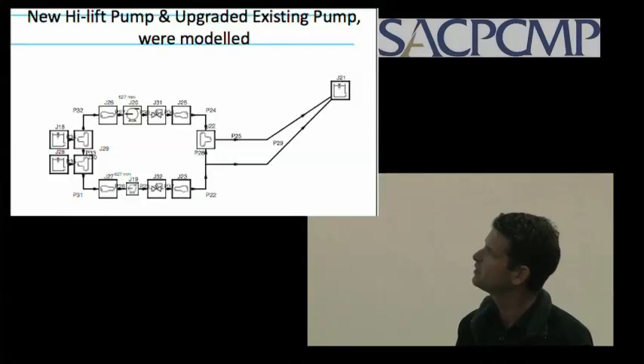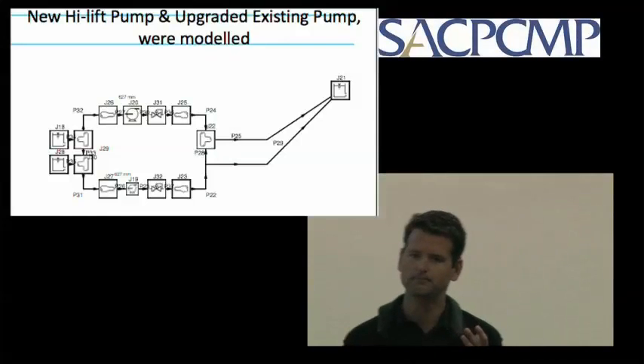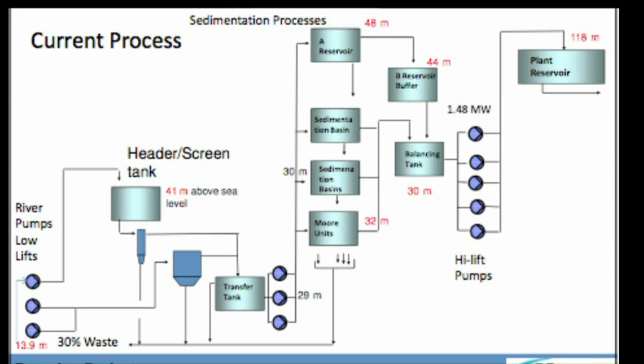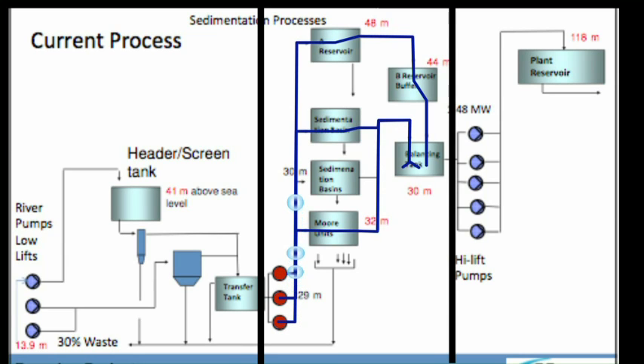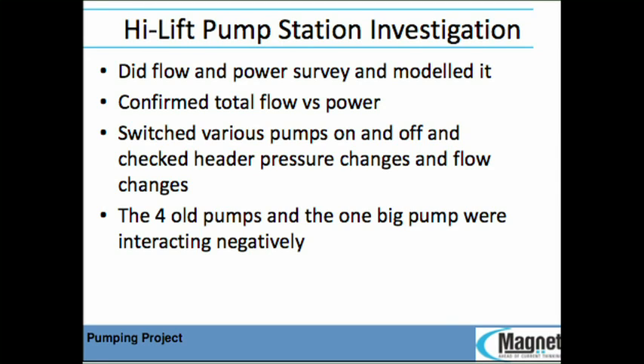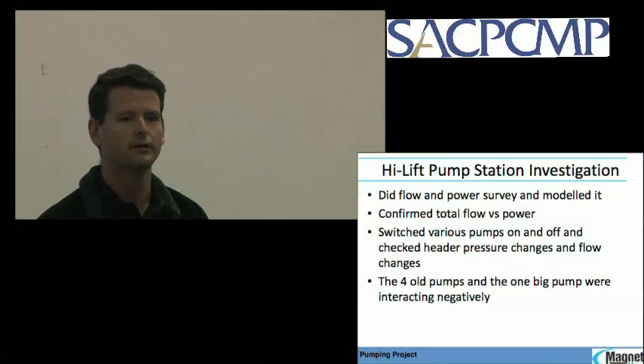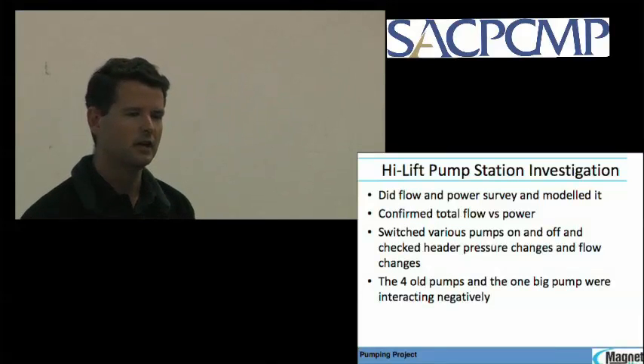The transfer pumps were also supplying this classic situation of pumping up to the A reservoir clarifier on the hill, 15 meters up, and the rest of the plants at the same level. So there was an opportunity there for energy savings. And then on the low lift pumps, there was some opportunity, because they were overflowing and wasting water all the time. On the high lift pump station, we did a whole flow investigation and power survey, and then we modeled that whole high lift pump station. And I think I kept on going because I was just so amazed at how bad it was. And I couldn't really believe the figures.